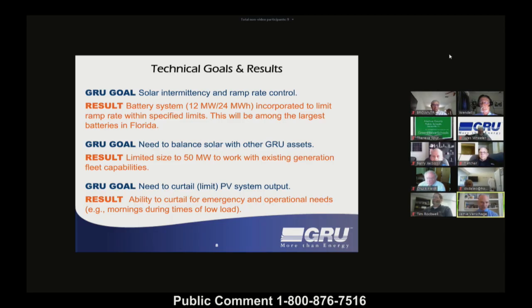Most of GRU's traditional generation comes from heavy turbines turned by steam or burning natural gas, connected to electrical generators. There are limits to how quickly you can ramp the electrical output of these rotating machines up and down before causing damage. Solar generation doesn't work that way—its output depends on sunlight hitting the panels, and its electrical output varies almost instantly with changing cloud cover. GRU's first technical goal was to get some level of control over solar intermittency and the ramping rate of the solar system's output.